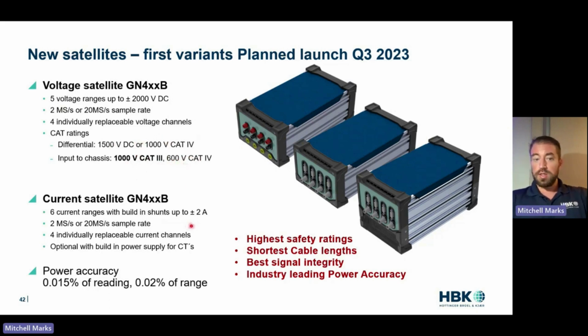Current satellite is more or less the same, except now we have a potential integrated power supply. With 6 ranges, power accuracy is going to be untouchable - 0.015% of reading plus 0.02% of range, and that's going to be real nice across the frequency spectrum.